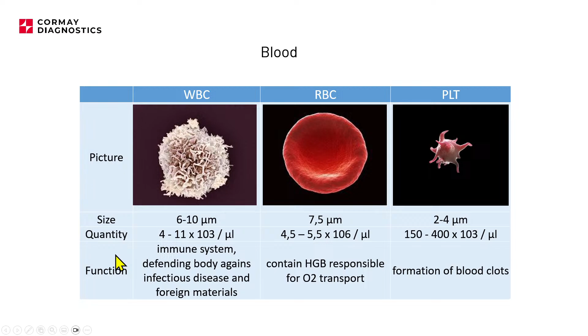And here on this slide, maybe you already know that, but just in case that this is not clear for you, device is making a series of dilutions. So first dilution is when the whole blood sample is put into the WBC chamber, and then device is adding, in the first step, diluent into this chamber. So this diluent basically makes a dilution in such a way that the number of particles in this solution is at such a level that the device will be able to correctly count them. By correct counting, I have in mind that each white blood cell will go through the aperture in such a way that the cells will not saturate the analyzer, right?